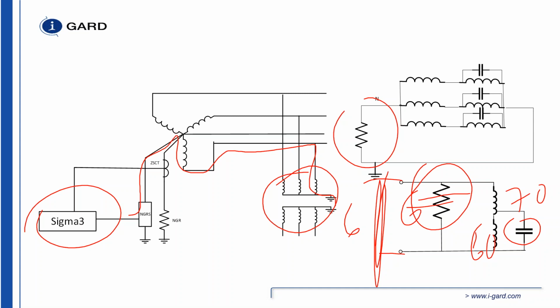So we can monitor that relatively quickly, because if that resistor is out of the circuit, we're only looking at the impedance of the 130 ohms here. If that becomes shorted, we're looking at 6 ohms equivalent circuit to 0 ohms equivalent circuit. And that's easy to detect as well, because we're going from 0 to, so we're actually exaggerating the change in that resistance, because we're going from a 6 ohm resistor in parallel with anything greater than that is going to be a 6 ohm resistor. A 6 ohm resistor in parallel with something that's smaller than 6 ohms is usually going to be smaller. So we can monitor a low resistance grounded system quite simply.